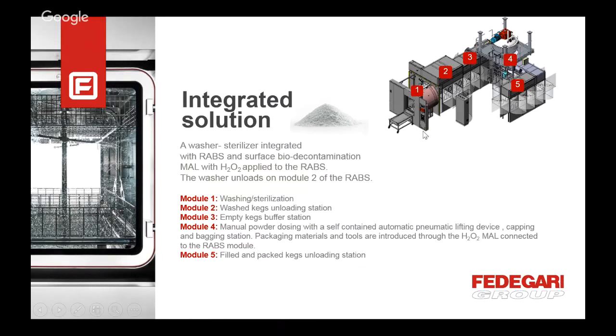You have the first module with the washing and sterilizing unit. It is a pressure vessel. This pressure vessel has a round shape because it is ideal for a washing cycle, because we can optimize the volume of the round configuration using the lower part as a collecting basin for the rinsing and the washing water, and decide to put some rotating nozzles to have a better coverage of all the material under process.